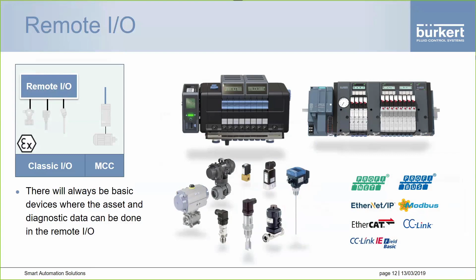They also have diagnostic capabilities. There's no longer just LEDs saying the valve has power. We've got indication of pilot operation, indication of field valve operation, cycle counters, wire break detection, timeouts, and a whole range of diagnostic information.